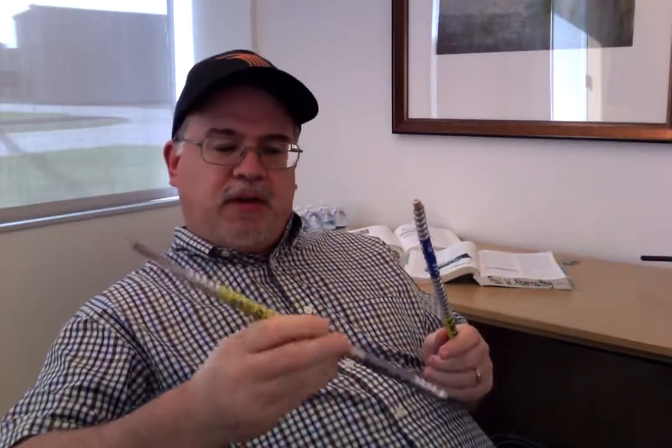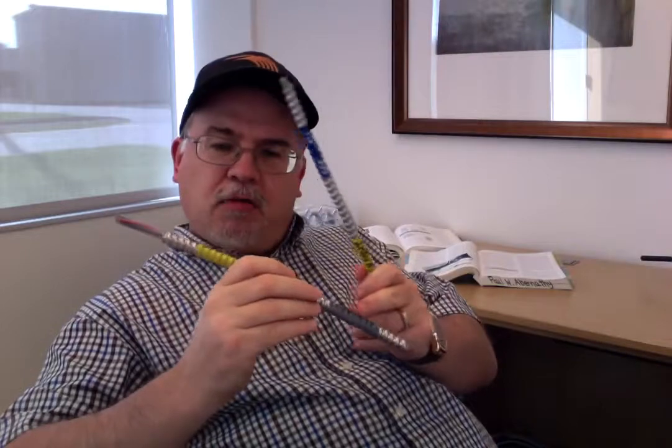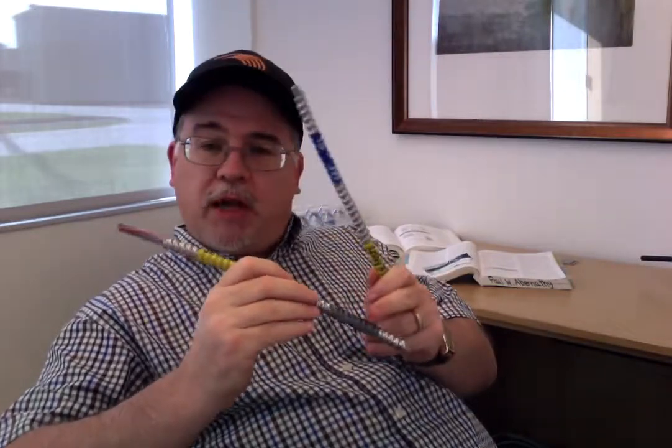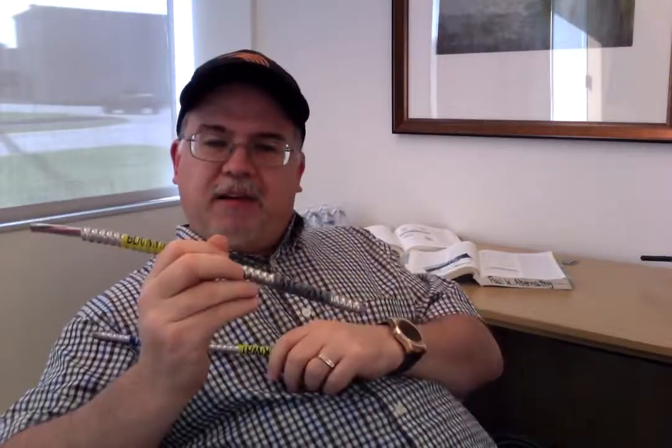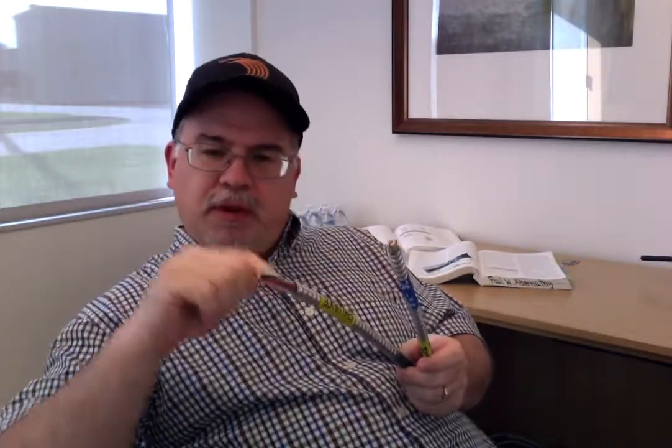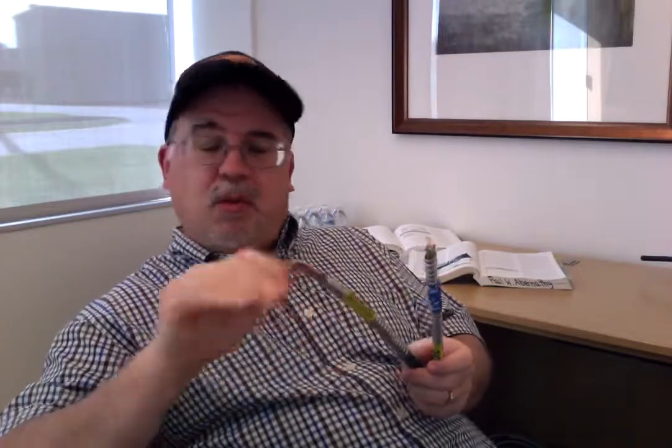Now let's look at these products here. Now this one here, which has a gray wrapped marking on it, and again, these are every 24 inches. The gray signifies that this is an aluminum armor, whereas the blue signifies that this is a steel armor. Now, we talked earlier about fittings. If I'm going to use a set screw type of fitting, I can only use that on the steel armor because it won't penetrate through the steel. In the aluminum, you can't use a set screw type of connector or fitting because it will penetrate through the aluminum and could damage the conductors, and it will damage the aluminum. So we can't do that.